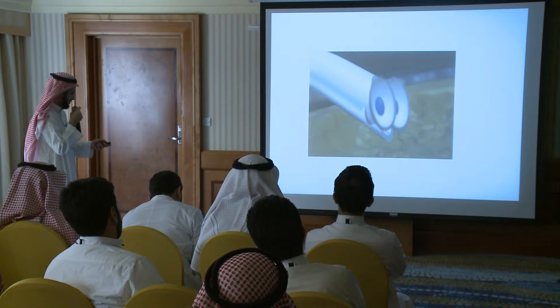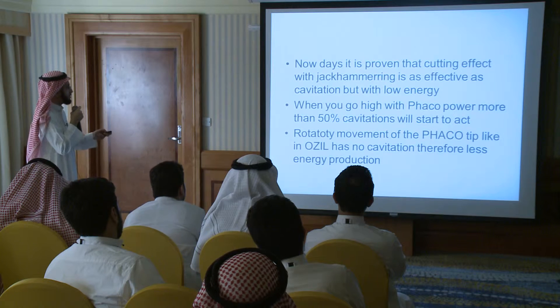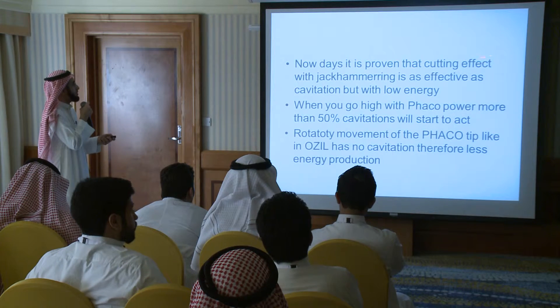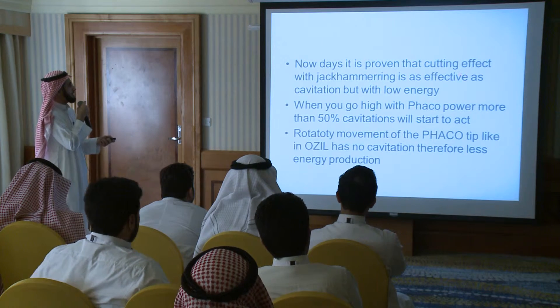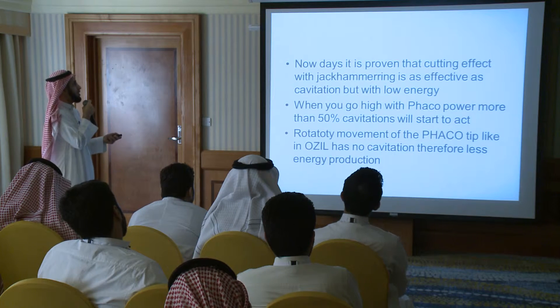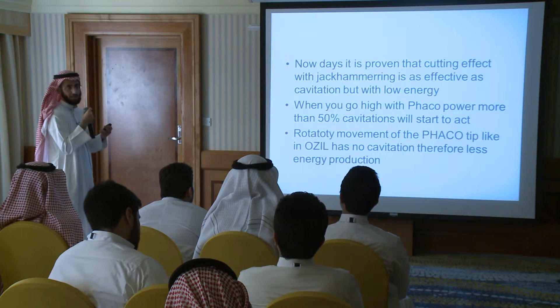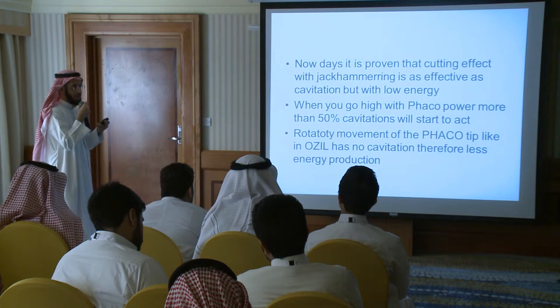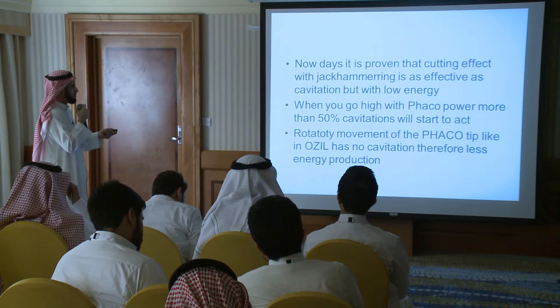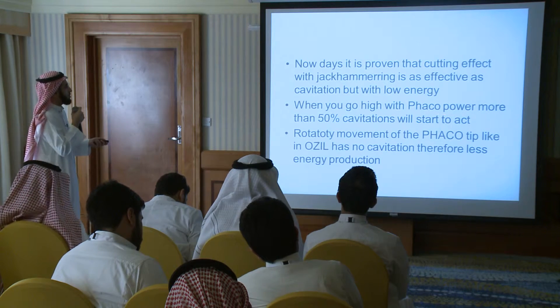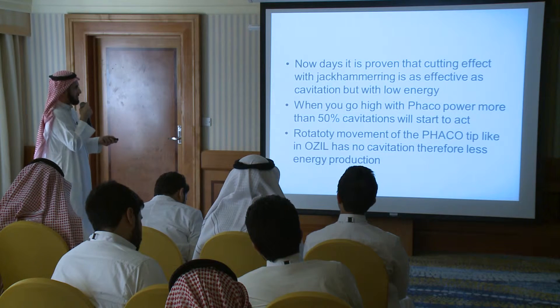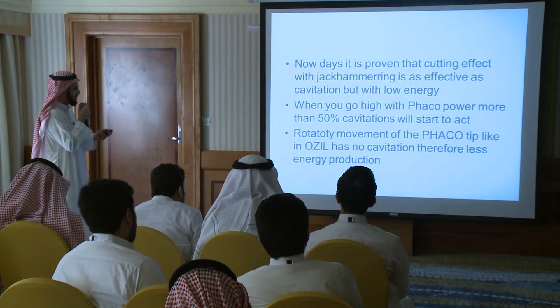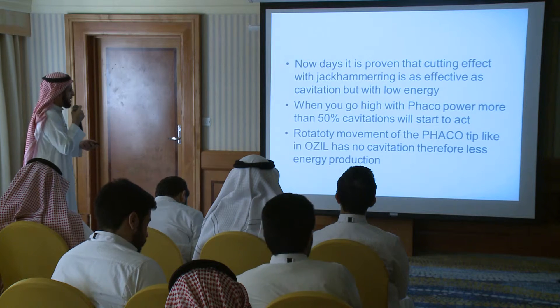It's now proven that the cutting effect with jackhammering is as effective as cavitation but with lower energy. So we prefer jackhammering because it has less energy compared to cavitation. We don't want cavitation unless the nucleus is very hard. When you go above 50% Phaco power, we will start having cavitation, which releases a lot of energy and may cause some damage.